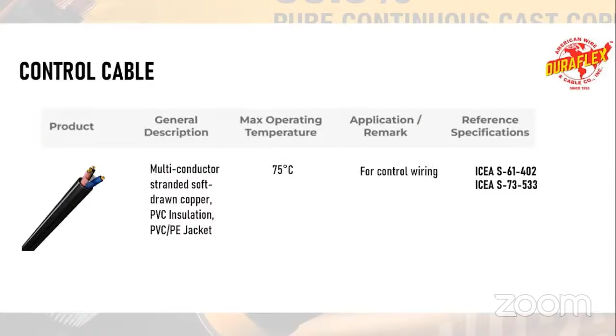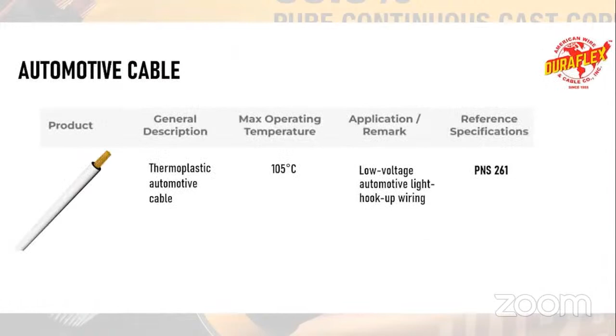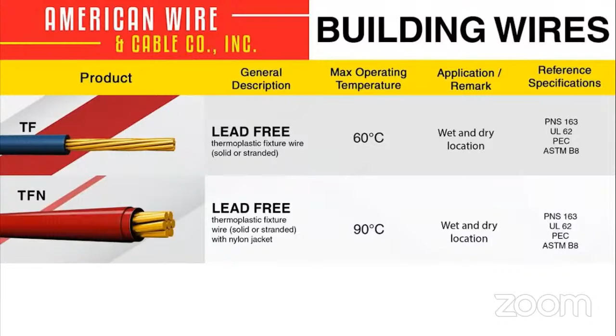Battery cable, thermoplastic battery cable, rated 105 degrees Celsius. Arc welding cable, thermoplastic welding cable, rated 105 degrees Celsius. Automotive cable, thermoplastic automotive cable, rated 105 degrees Celsius. And building wire. TF wires, lead-free thermoplastic fixture wire, solid or stranded, rated 60 degrees Celsius. TFN wires, lead-free thermoplastic fixture wire, solid or stranded with nylon jacket, 90 degrees Celsius.